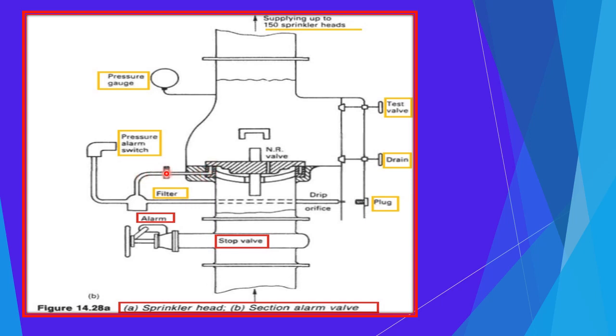Once the water passes through this filter, it is going to pressurize. Once it pressurizes, this breaks the circuit, and the test alarm, or the alarm for that particular system, will work. So the water which passes through this small bore pipe and the pressure alarm switch also gets activated, and this will give you the audio visual alarm.